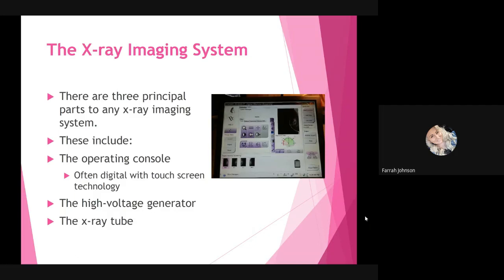So know that within your X-ray imaging system, there are going to be three principal parts. Those parts include first the operating console. This is typically digital with touchscreen technology when you're talking about mammo machines. You also have your high voltage generator, which provides the high voltage needed for X-ray production. And then you're going to have your X-ray tube, which will actually create the photons that we utilize to image breast tissue.